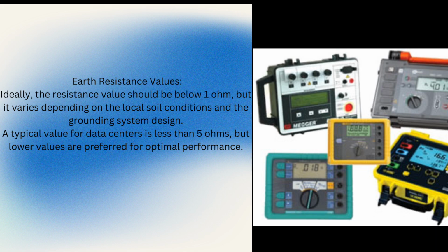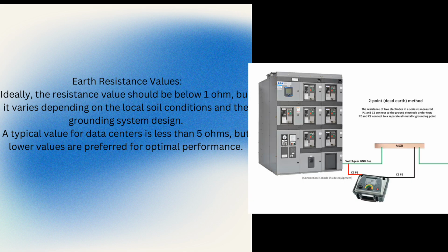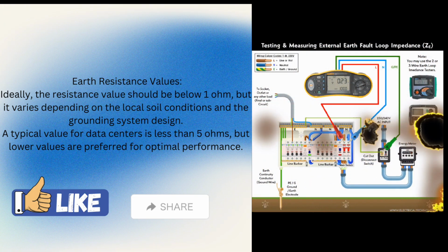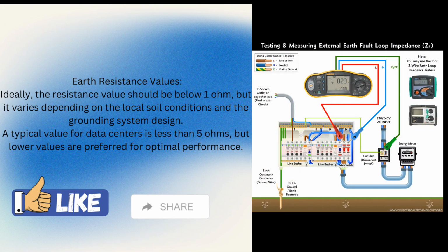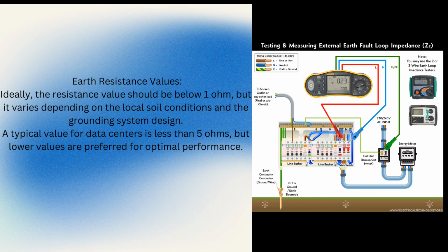Earth resistance values: ideally, the resistance value should be below 1 ohm, but it varies depending on the local soil conditions and the grounding system design. A typical value for data centers is less than 5 ohms, but lower values are preferred for optimal performance.